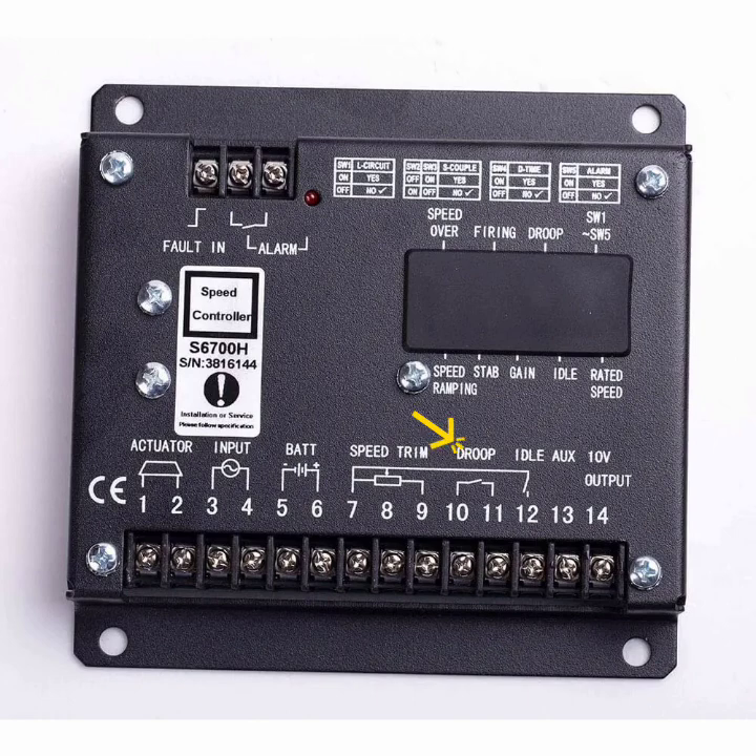Droop is used for on-load and no-load conditions. When we put a load on the engine, the engine frequency and RPM speed drop. When we adjust the droop setting, the engine compensates and returns to the rated speed. Droop is usually set from 3% to 5% only.